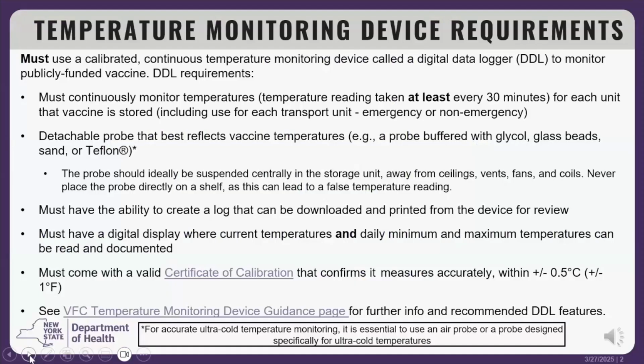All providers receiving publicly funded vaccine must use a calibrated continuous temperature monitoring device, also referred to as a digital data logger or DDL. The DDL must have continuous temperature monitoring capabilities and be recording a temperature reading at least every 30 minutes. The device must have the capability to produce a printed report that indicates continuous logging. The DDL must have a temperature display that is located on the device that can be accessed and checked by staff on a regular basis.